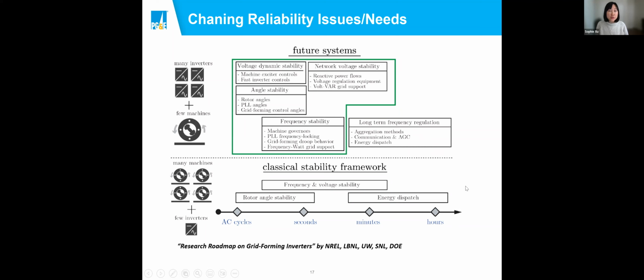And on top of these issues, I think there are two things that also need to be at least kept an eye on. One is the weak grid stability. The other would be the control interactions or control stability of the inverter-based resources. So these are the potential challenges that I could see from the future high renewable grid. And by all these, I'm testing. I did some tests on the grid forming inverter models in different categories of renewable issues, including voltage stability, which I think is more network voltage stability, potential angular stability, and frequency response.